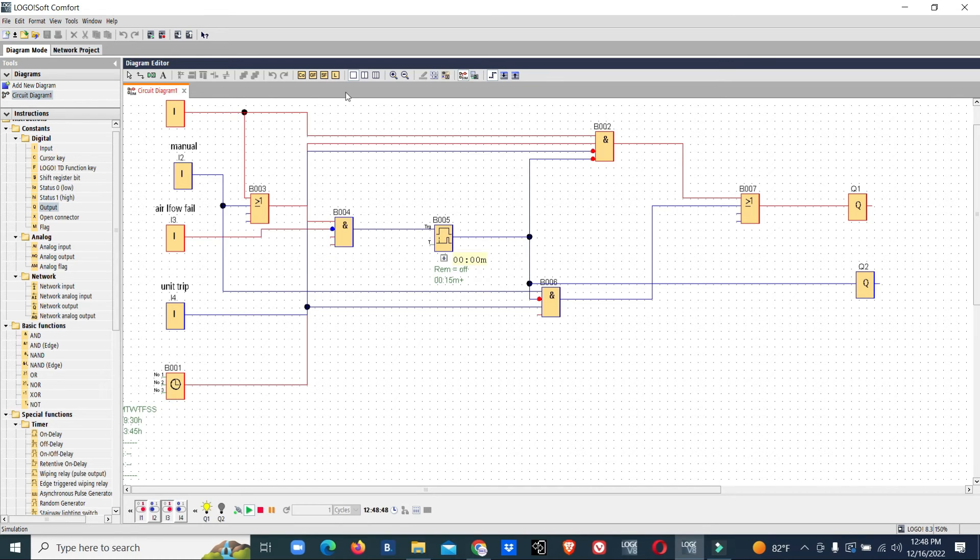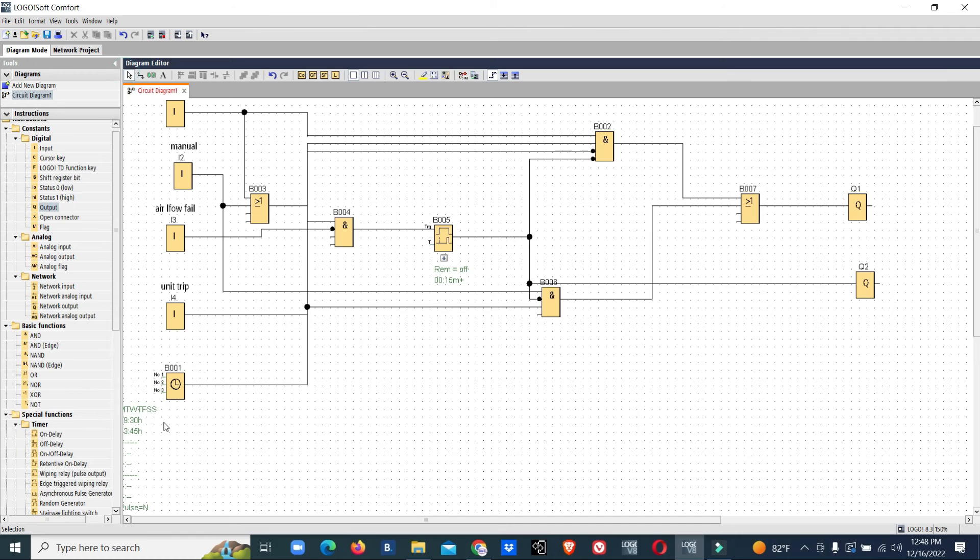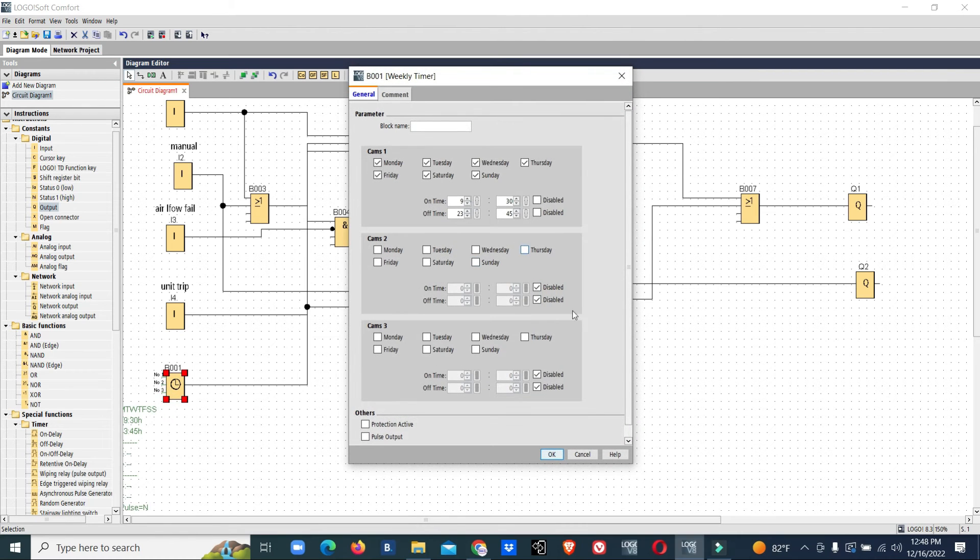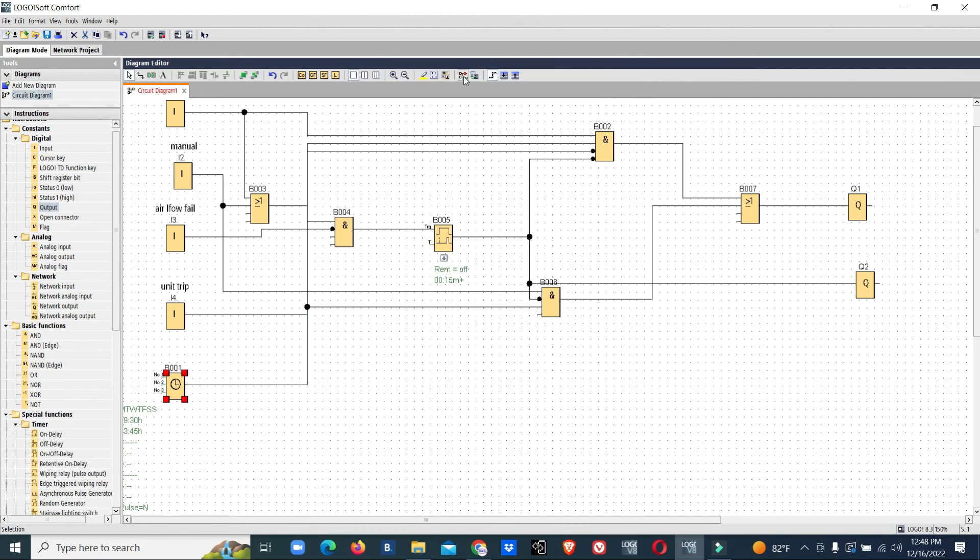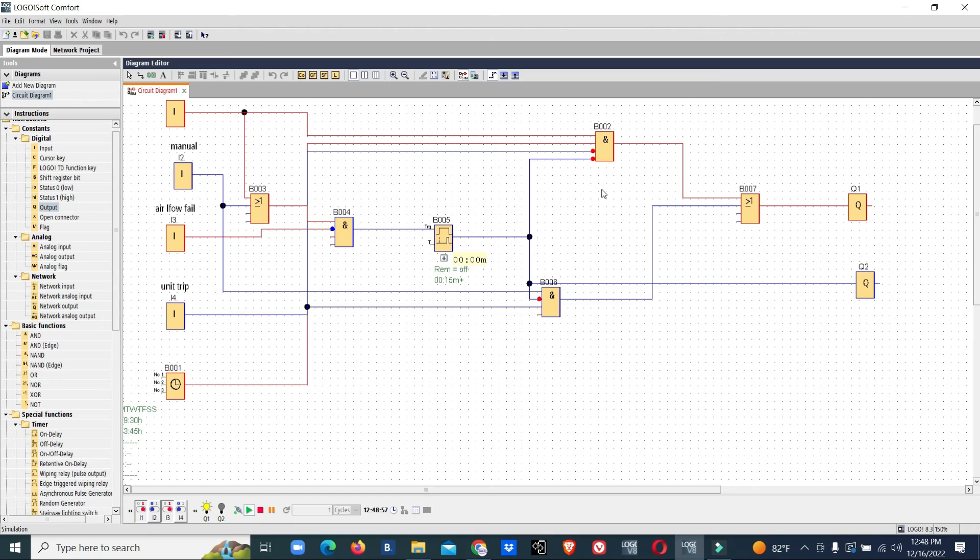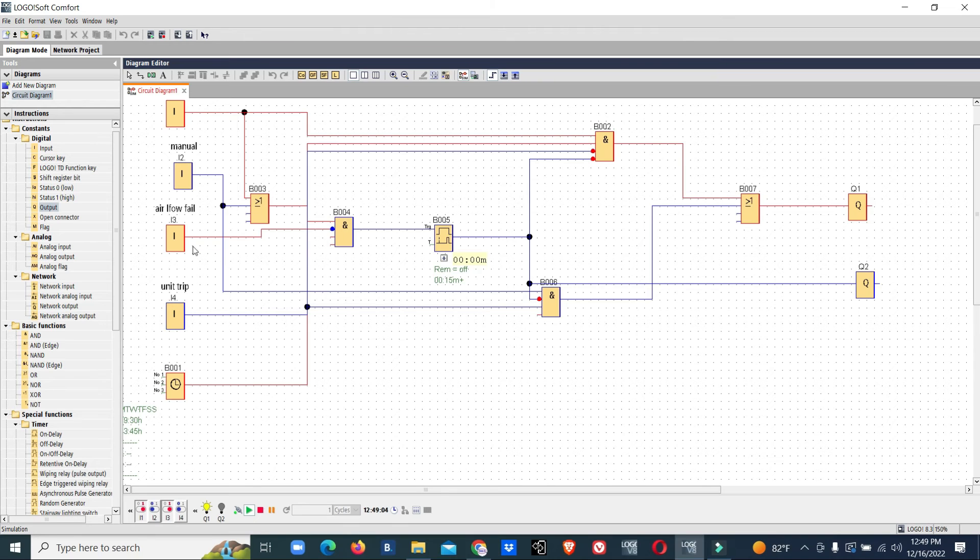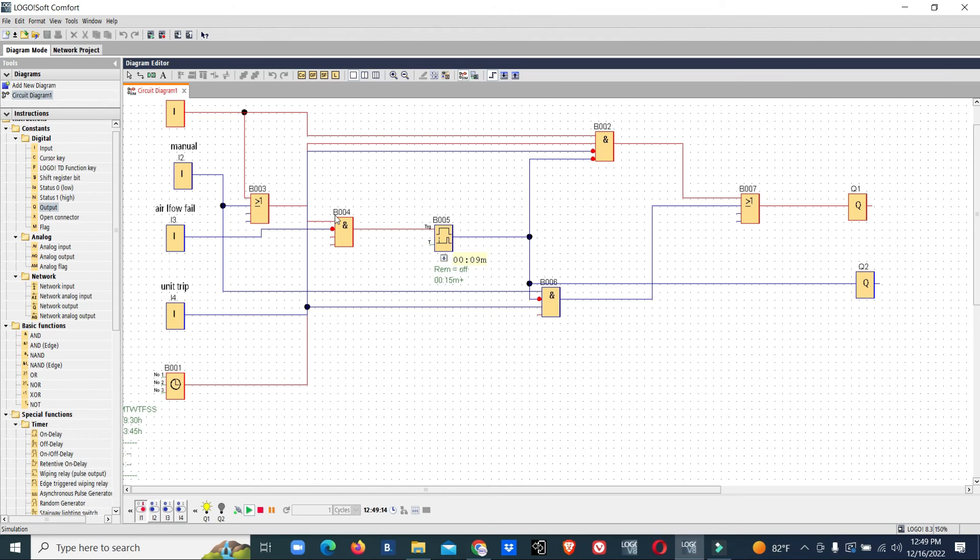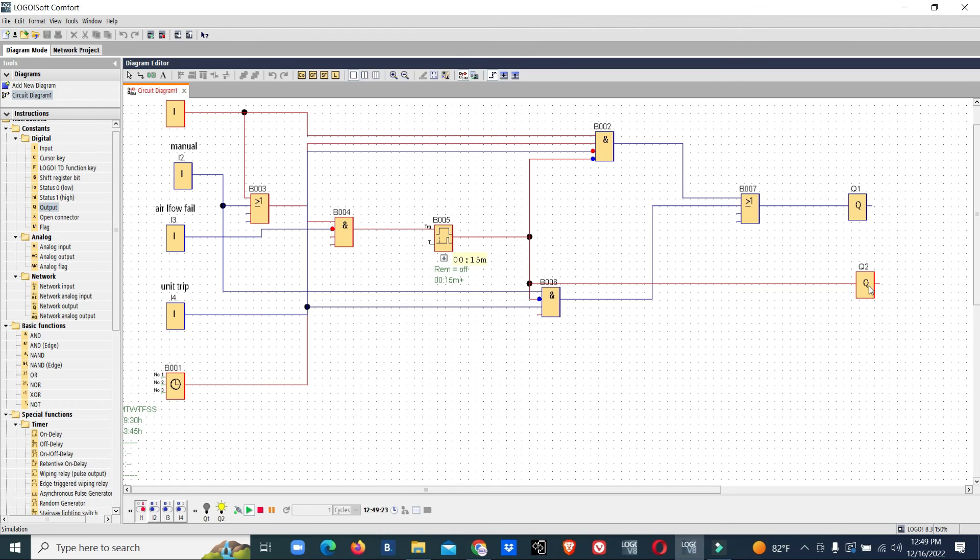This will keep on working till the time basis. If it reaches time 23:45, then it will stop automatically and restart the unit at 9:30. While running, if the unit trips, it will stop automatically. If the airflow fails, it will count the timer. Now the unit stopped—the output airflow fail has come. This is auto mode.